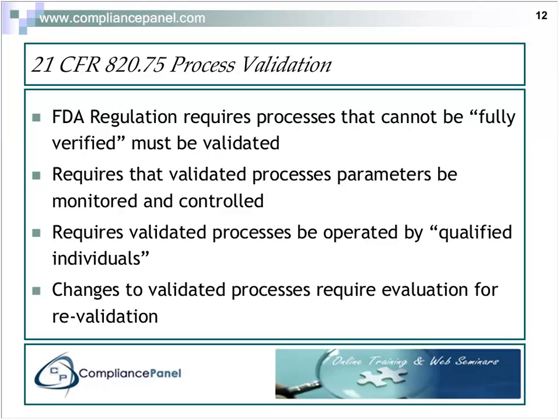It also requires in the regulation that any changes that take place to our validated processes require evaluation for revalidation. So if we make a change to a process, perhaps we've got a cost improvement, perhaps we have changed some material along the way, even changing from soft tooling to hard tooling, we need to evaluate that change to make sure it doesn't impact validation. And if it does impact validation, we'll have to perform at least a portion of that validation to demonstrate that we haven't adversely affected the ability of that process to consistently produce product.